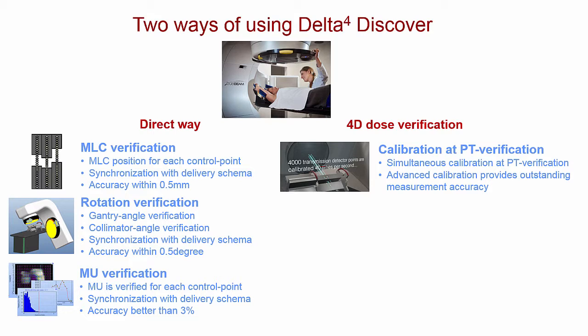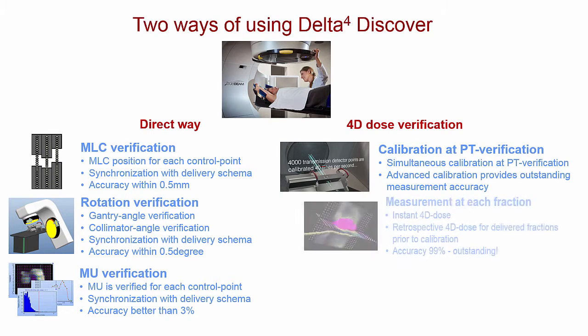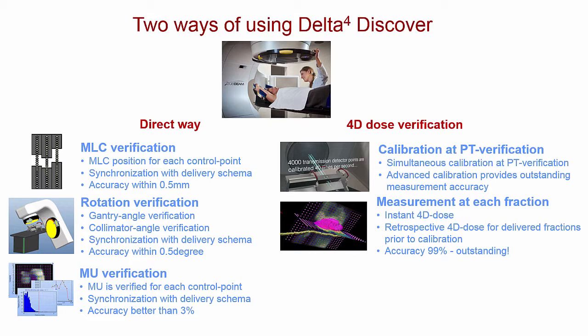If we want to go further than doing just the direct way for verification, we can do the 4D verification. The 4D verification requires a patient-specific calibration, and the Delta4 Discover system is then calibrated towards the pre-treatment verification system, so the Delta4 PT or the Delta4 Phantom Plus. When you've been doing that, you can measure at each fraction and get the 4D dose distribution, 3D dose distribution plus time resolution. The calibration can be retrospectively applied to the data you obtained with the direct way.